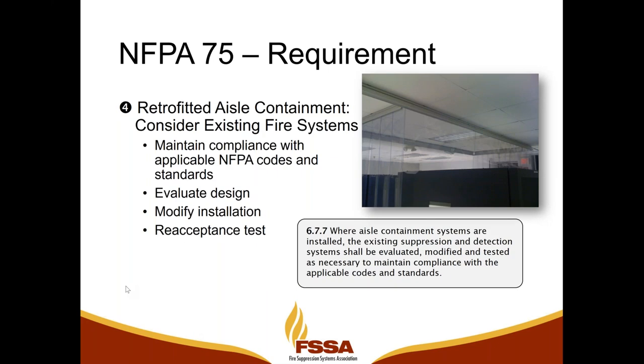For retrofitting aisle containment, there is a requirement that reads 6.7.7: where aisle containment systems are installed, the existing suppression and detection systems shall be evaluated, modified, and tested as necessary to maintain compliance with the applicable codes and standards. So ultimately, that's a comment in there that we may need to go back and retroactively adjust the fire protection systems to deal with the new aisle containment systems that are in place in the data center.